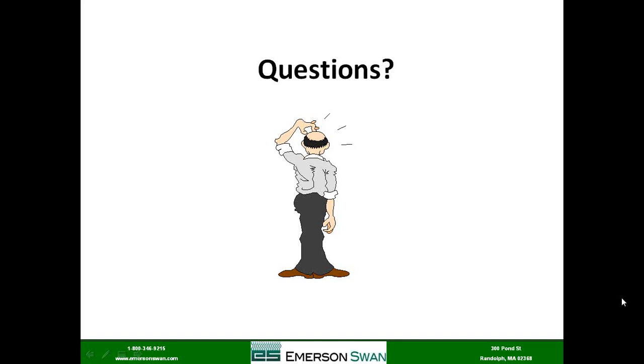So one of the things Bruce said is cleaning the system obviously is a good thing, but black iron oxide just exists in water, and there's not much you can do about that. So what we've done is try to take that service issue away. I hope that answers your question. Bruce, have you seen anything to add on that one? What we're starting to see now is that iron oxide problem showing up in the condensing boilers, and I think as time goes on, as we learn more, we're going to find that we need to address that issue.